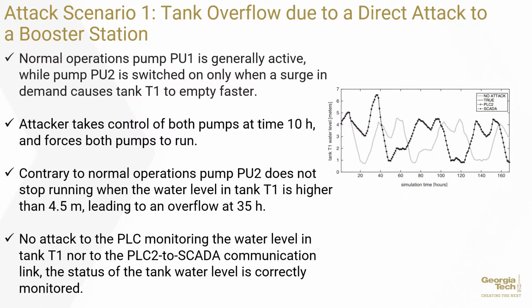This graph shows tank 1 water level versus the simulation time. Obviously, after time 10, there starts to be some divergence between the normal situation and the attack situation. After time 10, or 10 hours, we see that there is a divergence. Also, interestingly, this paper presents the measured value of water level 1 at PLC2 and SCADA. And as you can see here, since there is no attack on the PLC to SCADA link, there is no significant difference between the value shown at PLC2 versus SCADA.